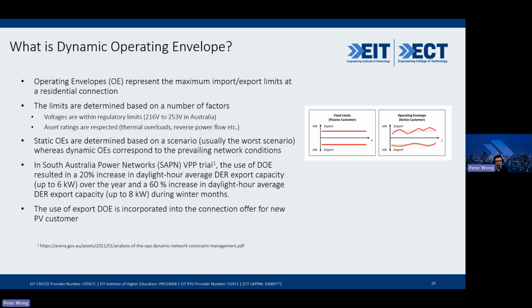If we don't have a dynamic operating envelope, then a static operating envelope is probably the proxy we have. If you have static operating envelopes, the utility has to determine them on the worst-case scenario, because it's static, so you have to cater for the worst case. Whereas if we use dynamic operating envelopes, they are constructed based on the prevailing network conditions. So a dynamic operating envelope, especially from an export perspective, is likely to allow more export into the grid, instead of looking at the worst conditions, which is maximum generation and minimum load, for example, which might only happen during a very short period of time, or on not many days in a year. So the dynamic operating envelope certainly makes sense.